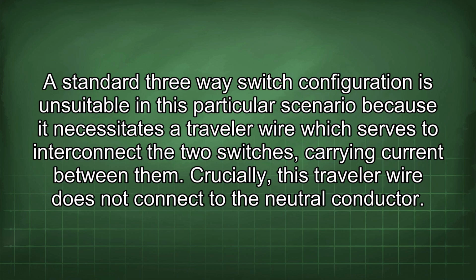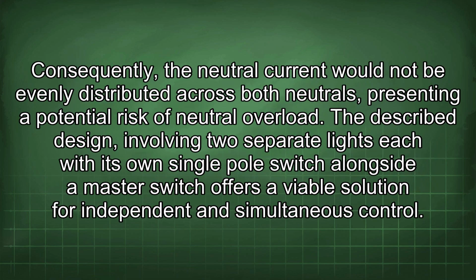Crucially, this traveler wire does not connect to the neutral conductor. Consequently, the neutral current would not be evenly distributed across both neutrals, presenting a potential risk of neutral overload. The described design, involving two separate lights each with its own single-pole switch alongside a master switch, offers a viable solution for independent and simultaneous control.